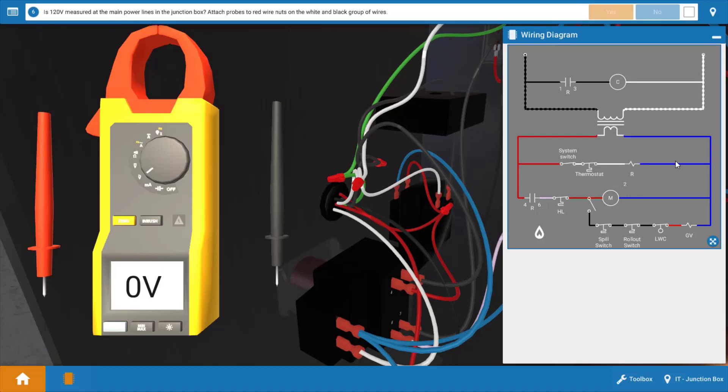And you know replacing the transformer without checking these will result in the new transformer suffering the same fate. So I always take a brief resistance check of the low voltage loads to make sure I have a measurable resistance across them.